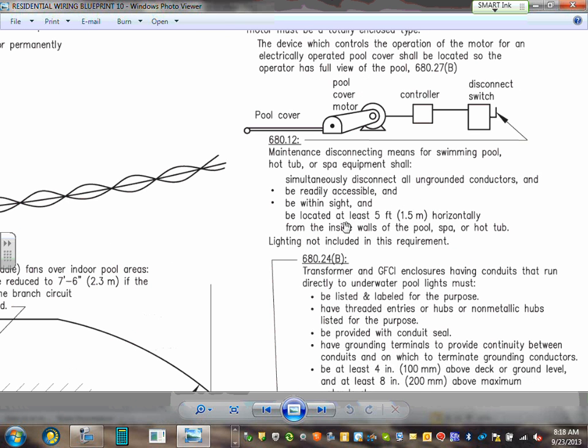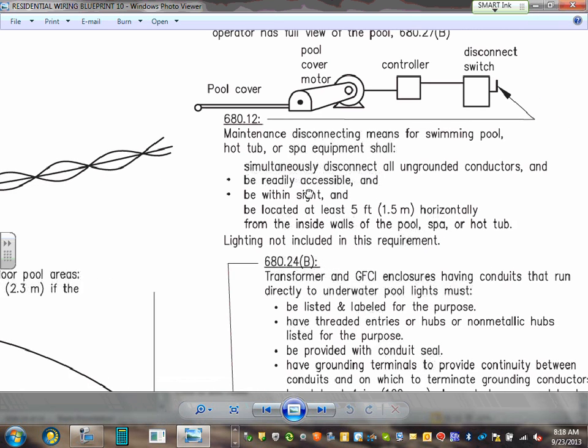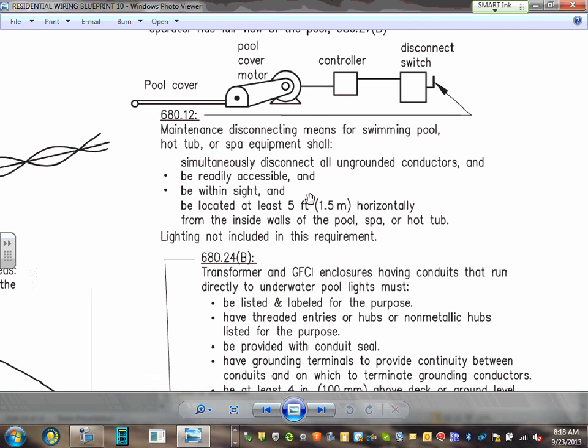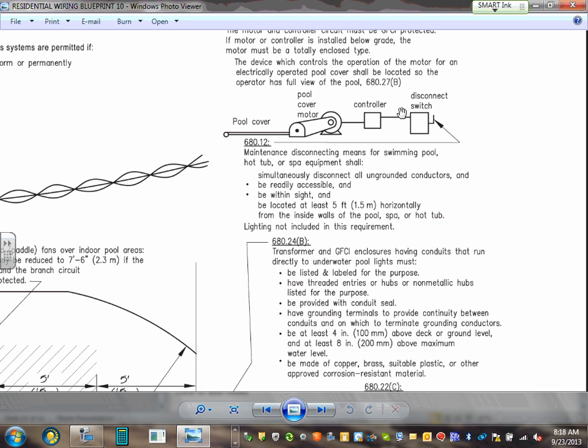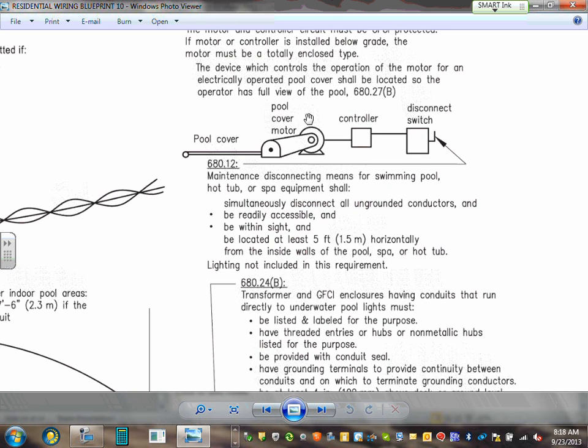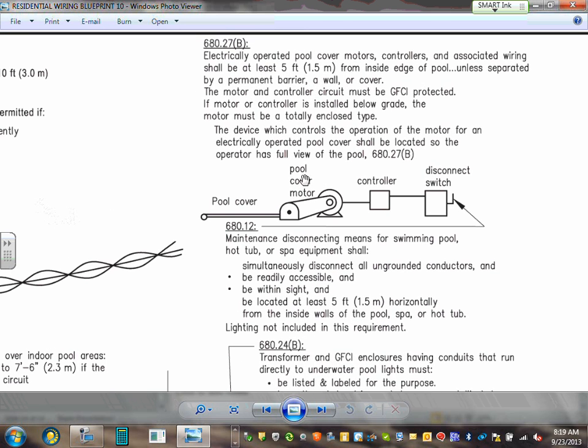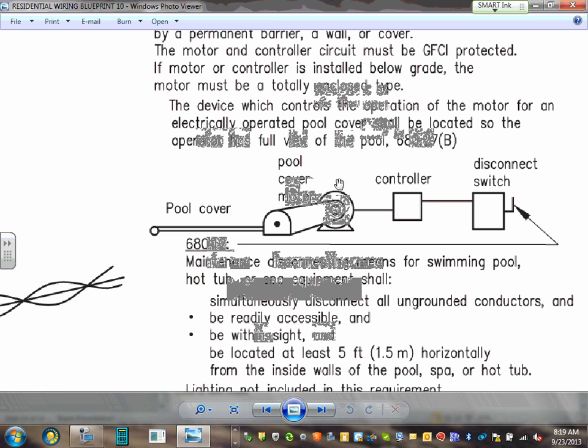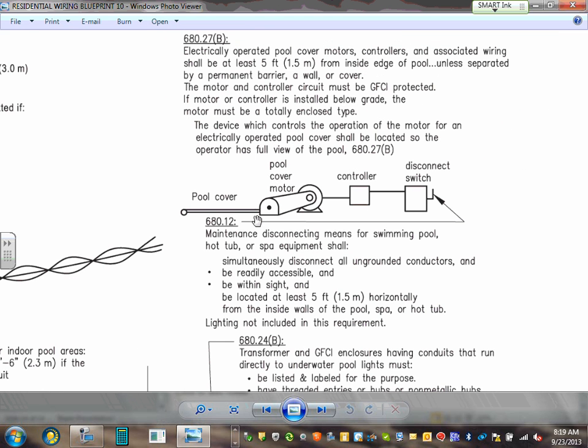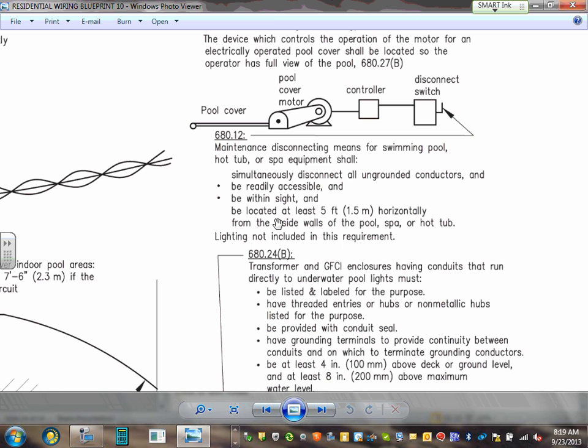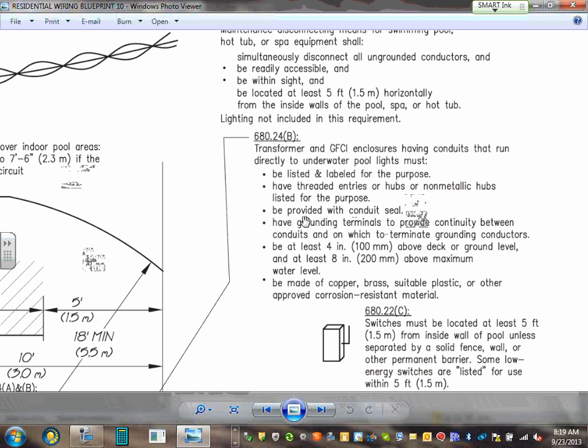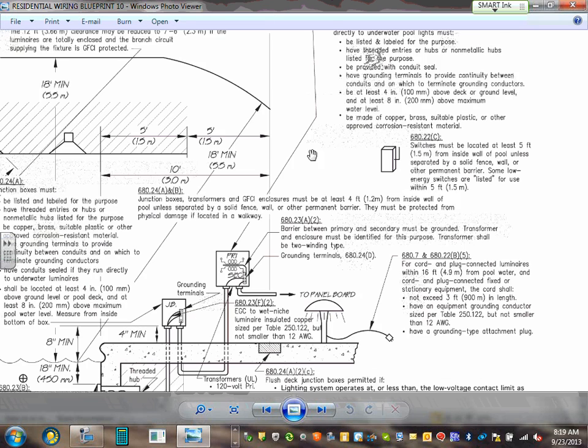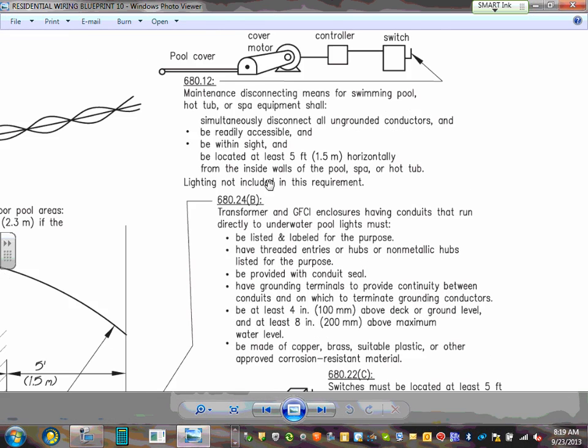Maintenance disconnect switches for swimming pools, hot tubs, and so forth. You have to have a maintenance switch that is readily accessible, within sight, and located at least 5 feet horizontally from the inside wall of the pool and the hot tub for disconnecting the equipment. This is for the cover, for example. The motor, if you have a cover for a swimming pool, you have to disconnect the controller within sight, at least 5 feet horizontally from the inside wall of the spa and the hot tub. Transformer enclosures. This is for the GFCI for your transformer.